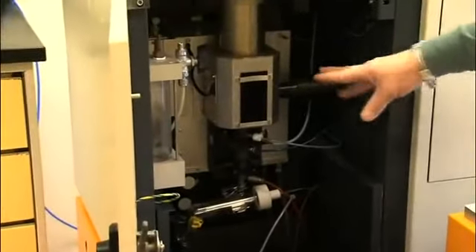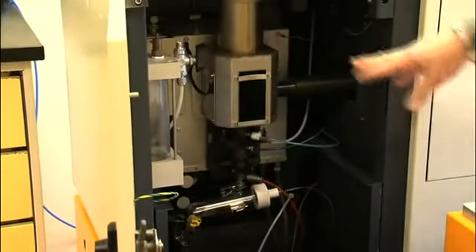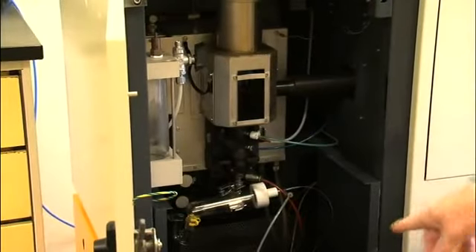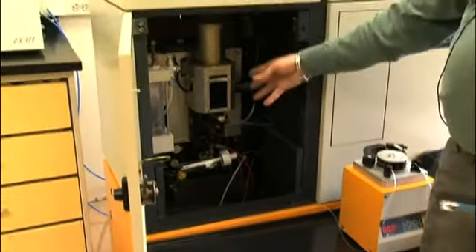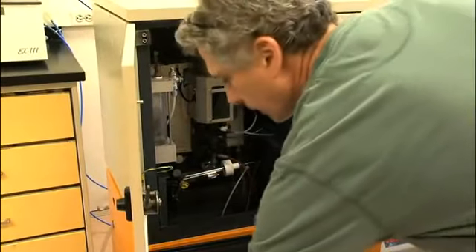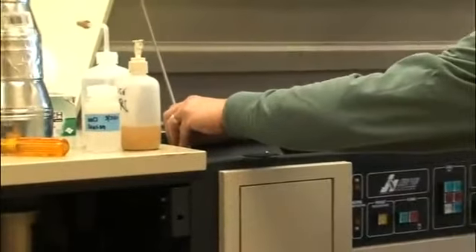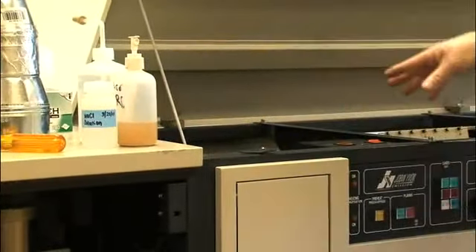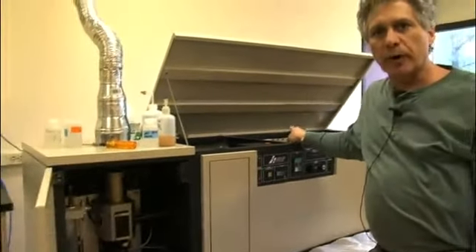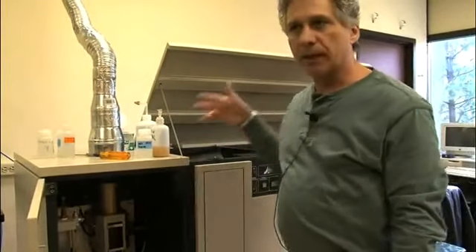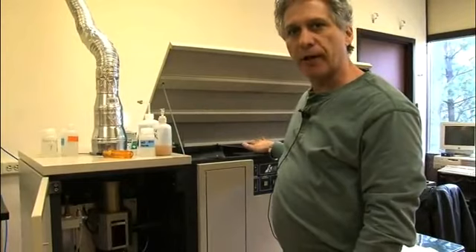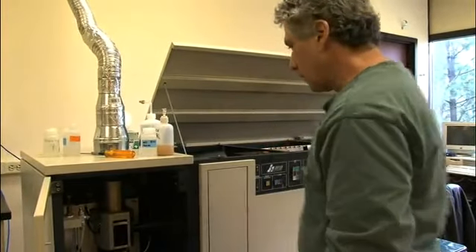I'm going to take this all out so you can see it better. You have your plasma generation, which consists of electronics down below, which create the argon plasma. And then underneath here you have your light analysis, which consists of a monochromator, which separates the white plasma light into all your wavelengths that you're going to look at for each individual element.